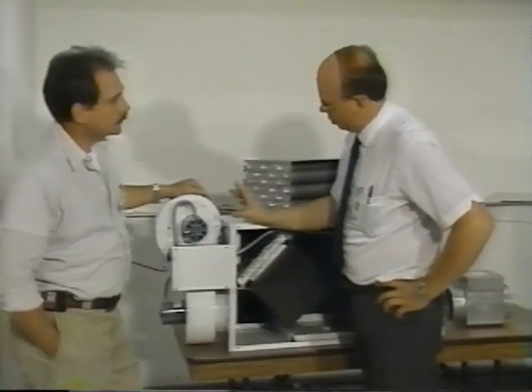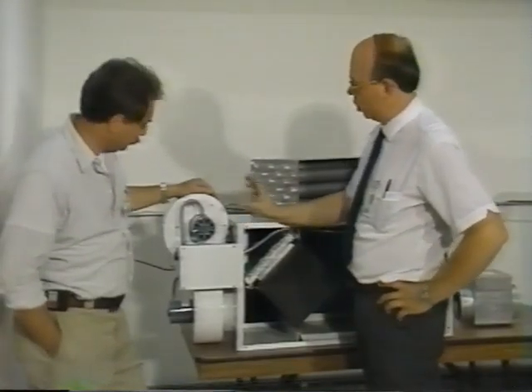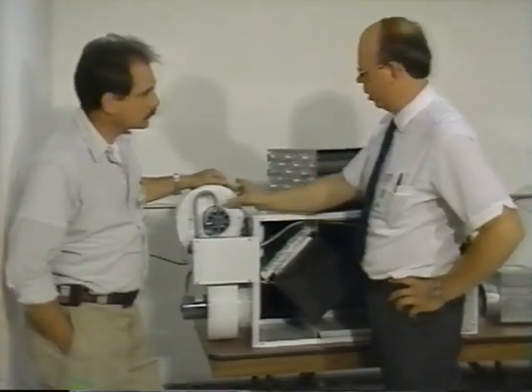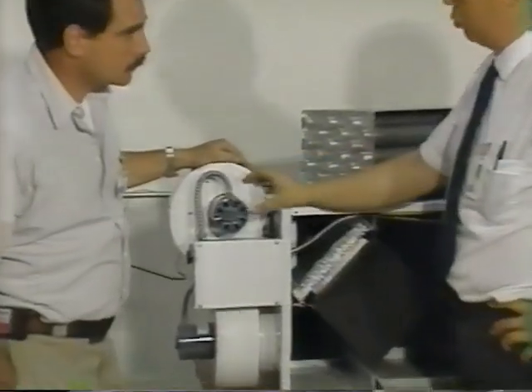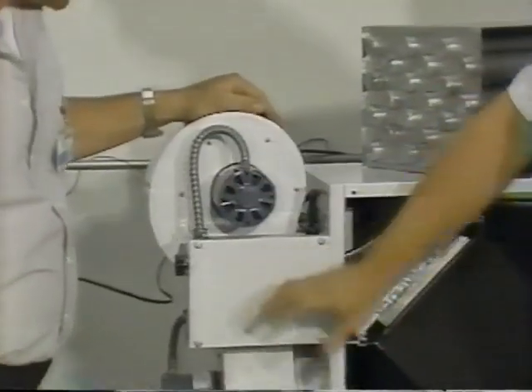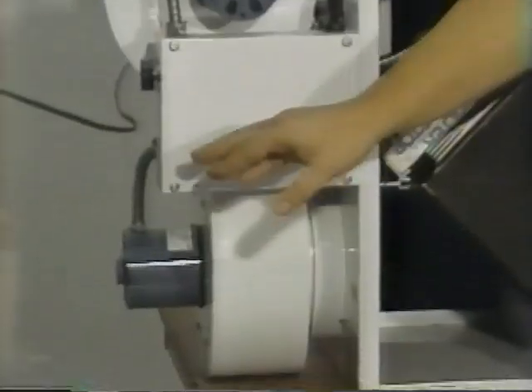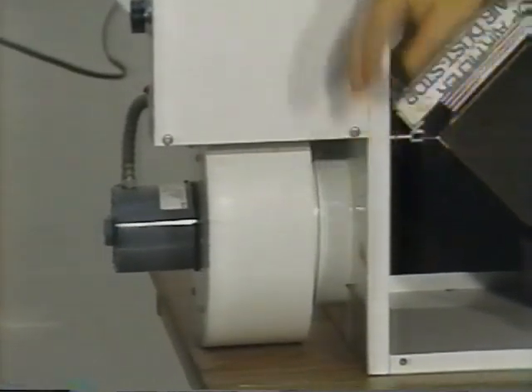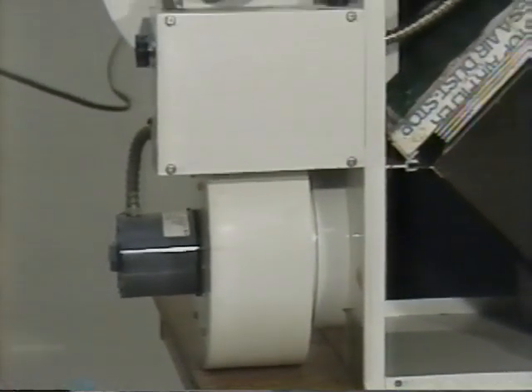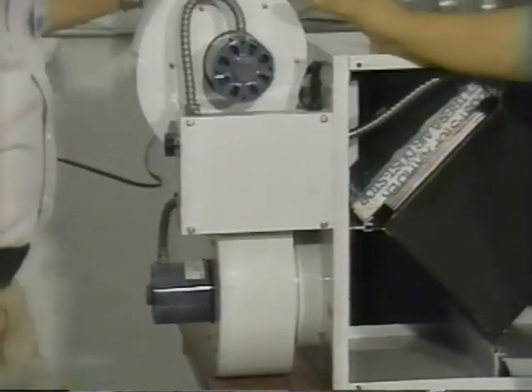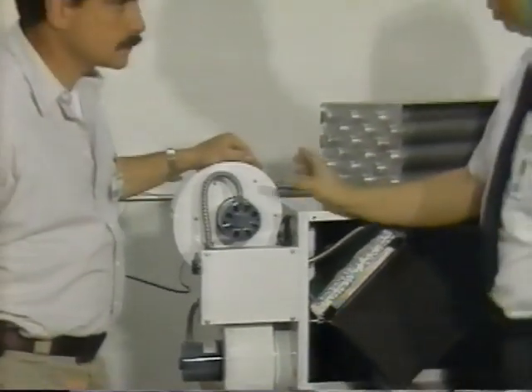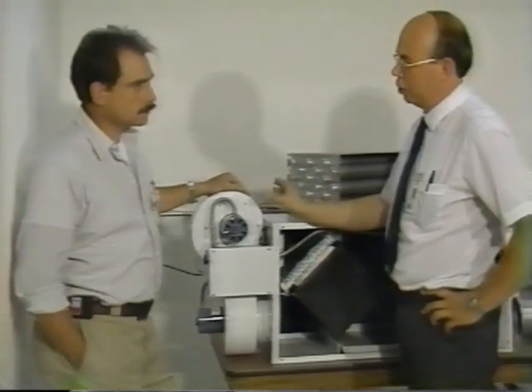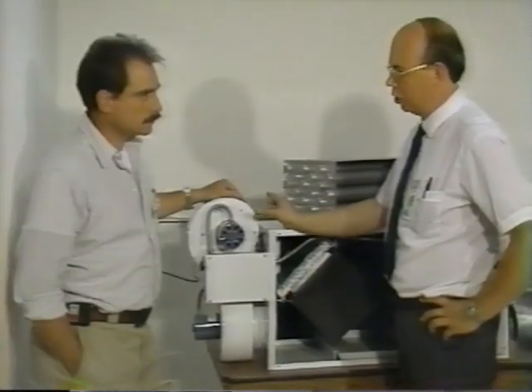Okay. First thing we have on the end here is the fans. The unit does two things. It basically takes air from the house, exhausts it out through this fan to the outdoors. It also pulls in fresh air from the outside through the heat exchanger and dumps it into the house. It's very important that these fans are sized to move the same amount of air. Balanced system. That's right.